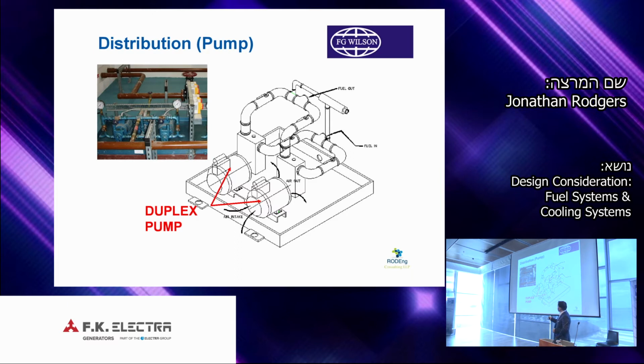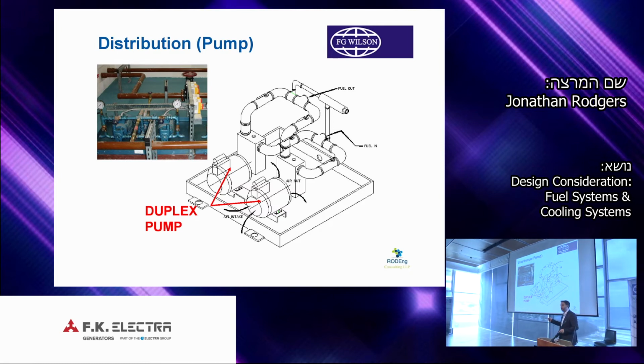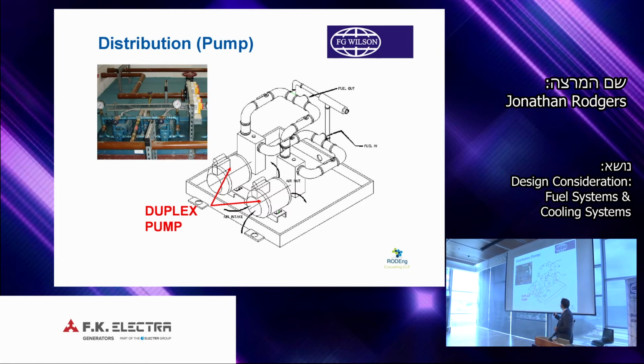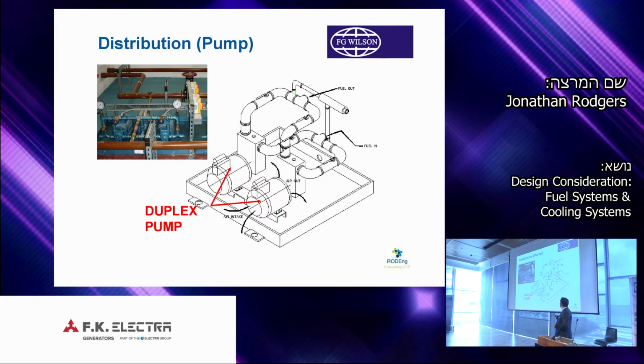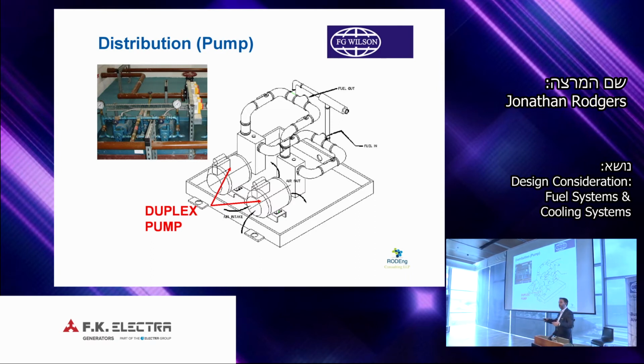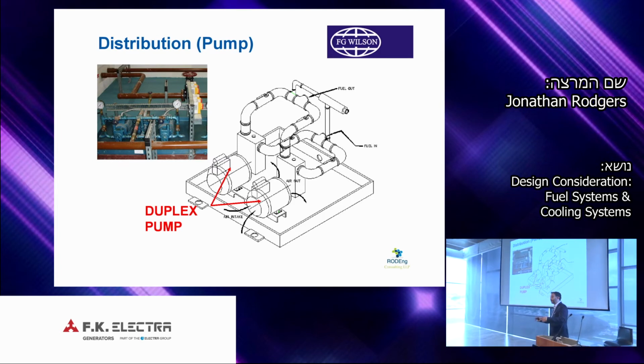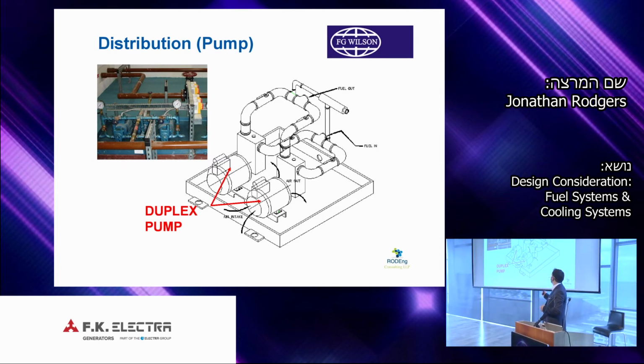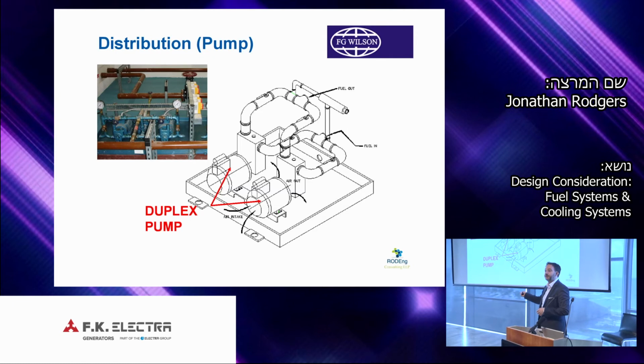So this is what these duplex pump kits look like. This is a typical data center pump arrangement. Just graphically, this is what it looks like with its tray. We have clearance for air intake into the motor of the pump, and then we will have a tray for collecting any drips or spills with an alarm to signal that there is a spill or a leak.